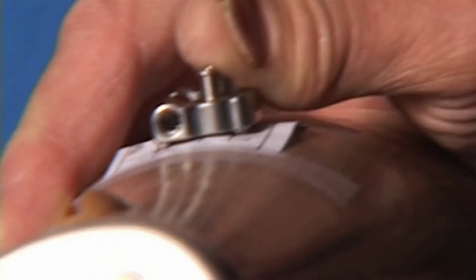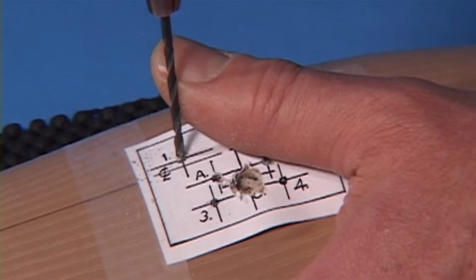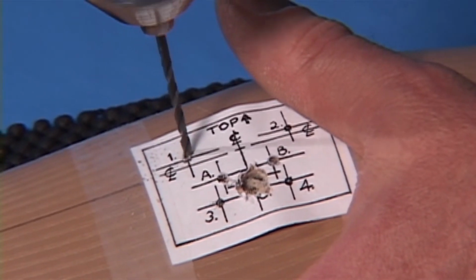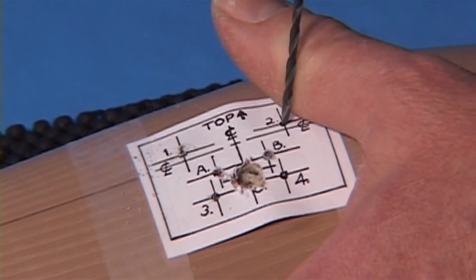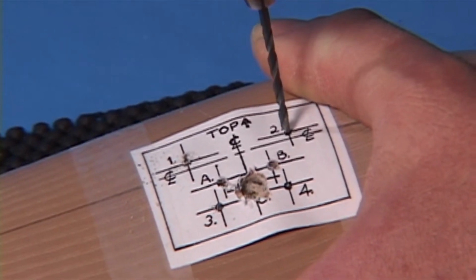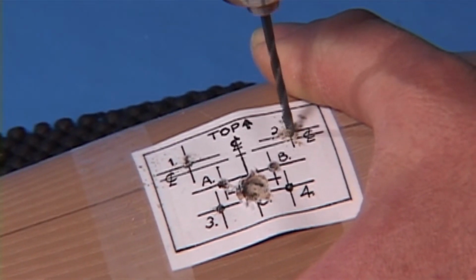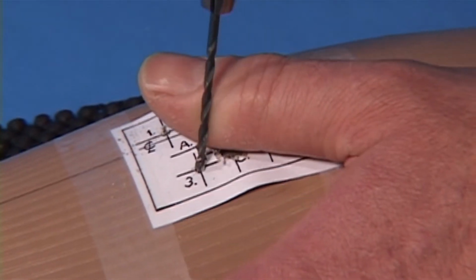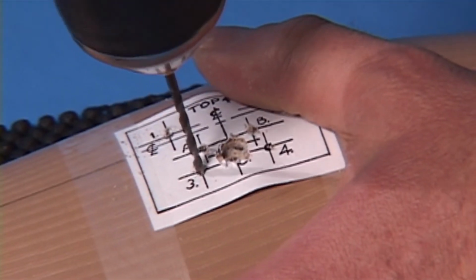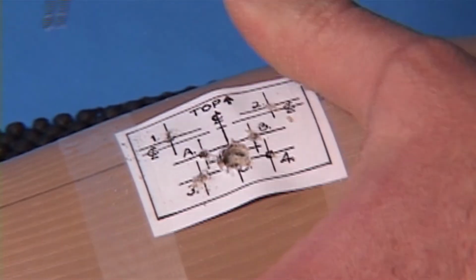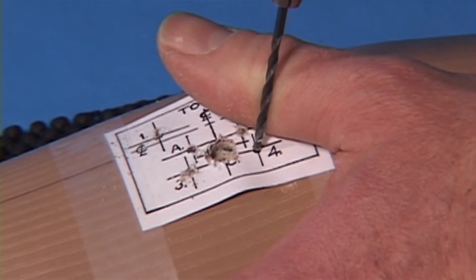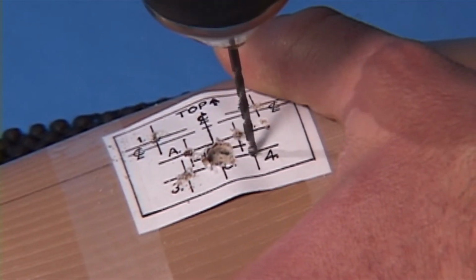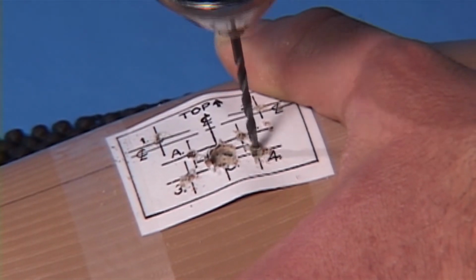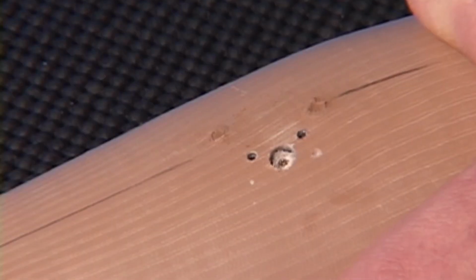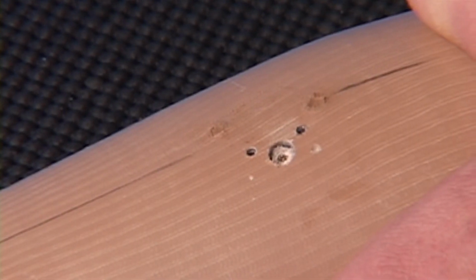If the structural base and its feet don't accurately fit the prosthesis surface, make 4 5/64 inch drill point depressions at the numbered hole locations. Normally only minor depressions are needed, and the feet should fit into these shallow holes. This allows the bottom of the structural base to touch the prosthesis along the center line firmly without rocking. The outside curvature of the prosthesis will determine if you need to make this modification. Remove the template and clean the prosthesis if necessary.